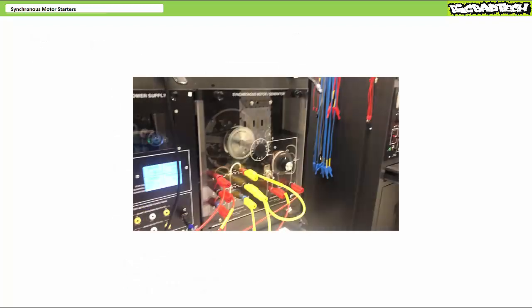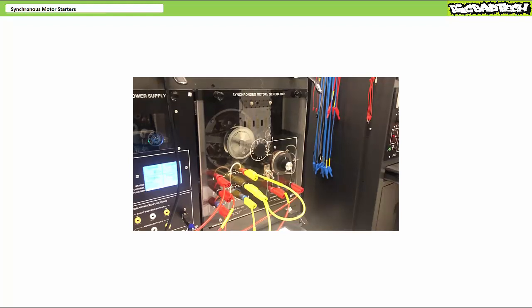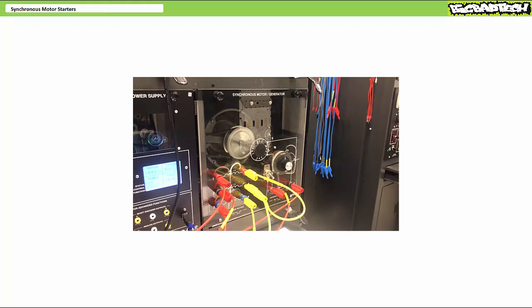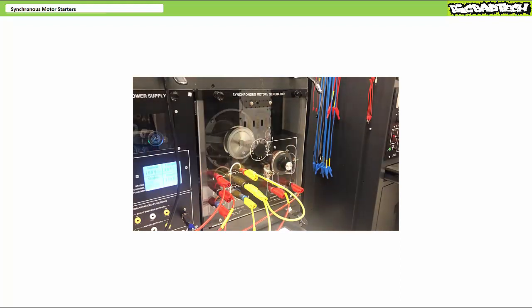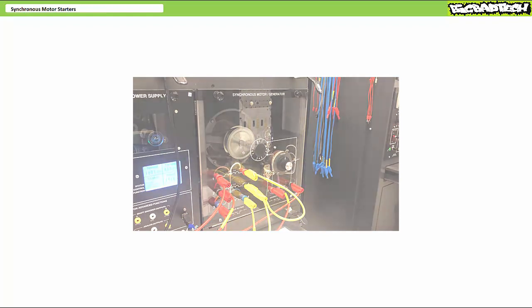Here's an entirely manual implementation of a synchronous motor starter using amortisseur windings. When I energize the stator field only, the cage-like amortisseur windings act like the cage of a squirrel cage induction motor, and the motor accelerates to near-synchronous speed. When it's close enough, I energize the rotor field winding, and the rotor locks into the stator and starts turning at synchronous speed.